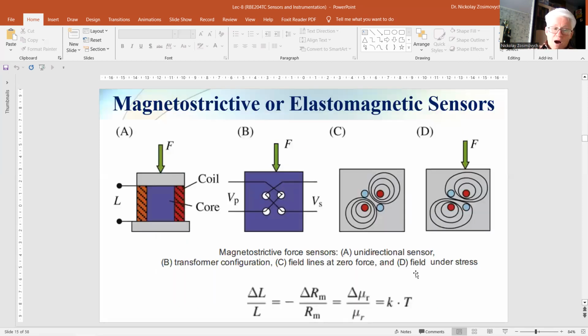A magnetostrictive, or magnetoelastic, or even elastomagnetic sensor is based on the change of the magnetic flux in a magnetic material due to deformation. Therefore, the effect is mainly used for force sensing. Basically, two different magnetoelastic sensor systems can be recognized: uni- and multi-directional. Sensors of the first type consist of a coil with usually a cylindrical core from a suitable magnetostrictive material, as you can see in figure A at the left part of this slide.